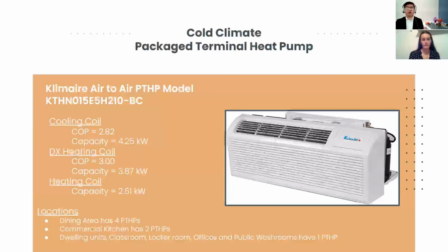Now, with regards to the actual PTHP model that we had selected, seeing as it is an air-to-air model, this would have to be installed against an exterior wall for each dwelling unit, as well as every other zone that it would be found in. Now, in particular, every zone, barring certain ones, is using only one PTHP installed inside of it. The other ones being the dining room, corridors, as well as the commercial kitchens. The dining room having 4, the commercial kitchen having 2, and then each corridor of the actual building having 2 as well, each located inside.